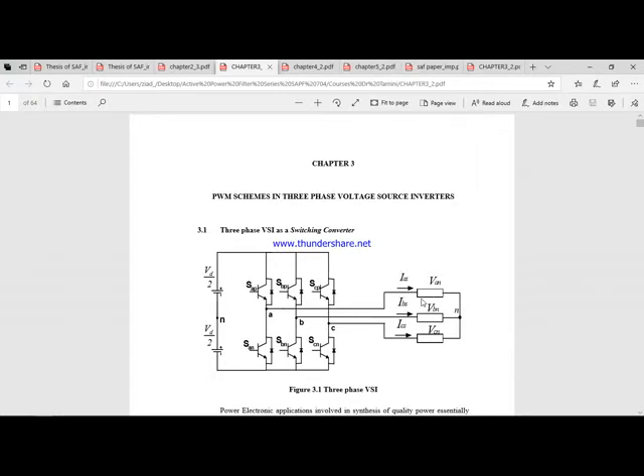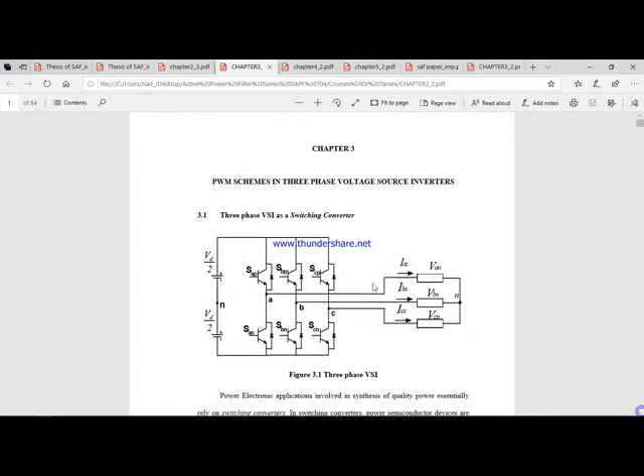Following this perturbation, I want to compensate it. For example, if I have a SAG perturbation — a decrease in voltage on the main circuit — I have to increase this voltage on the load by using this inverter. I have 2 types of inverter: the VSI or voltage source inverter, and the CSI or current source inverter.